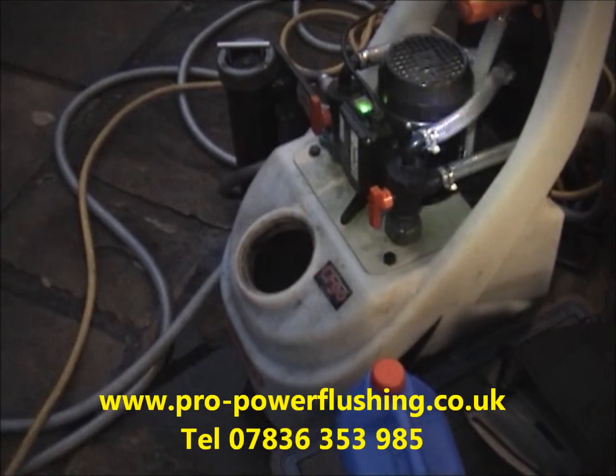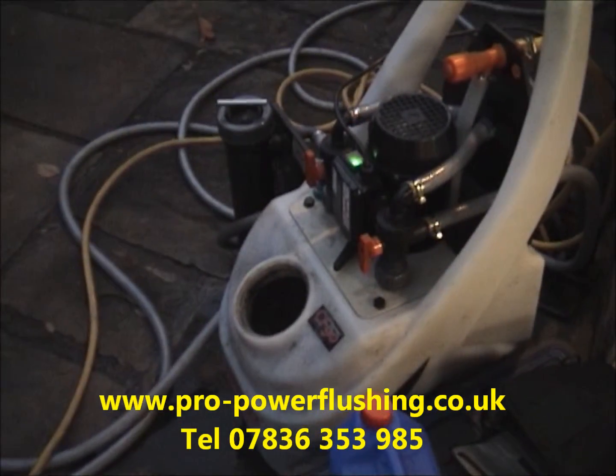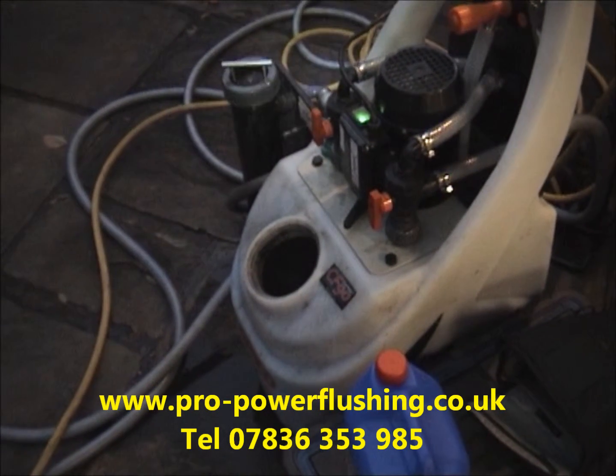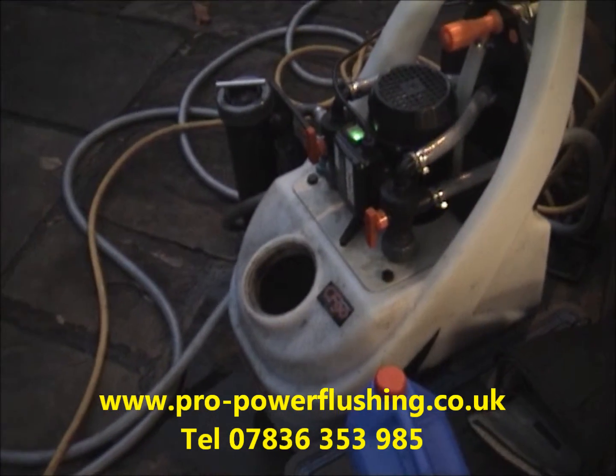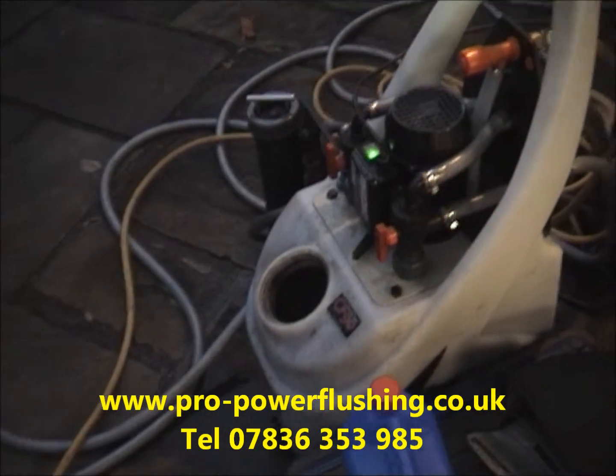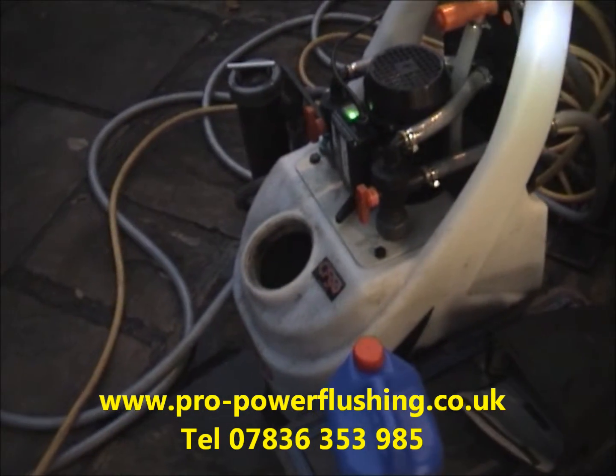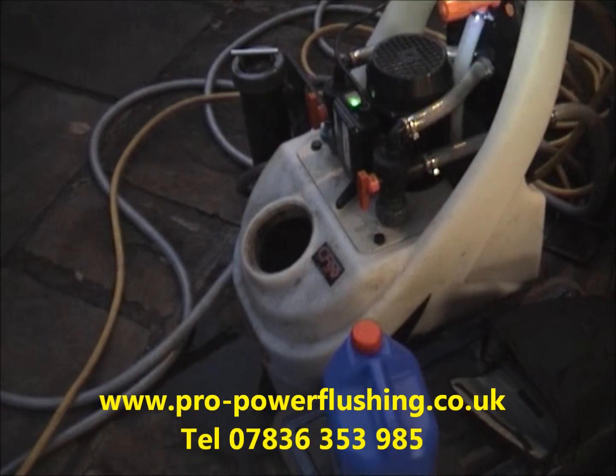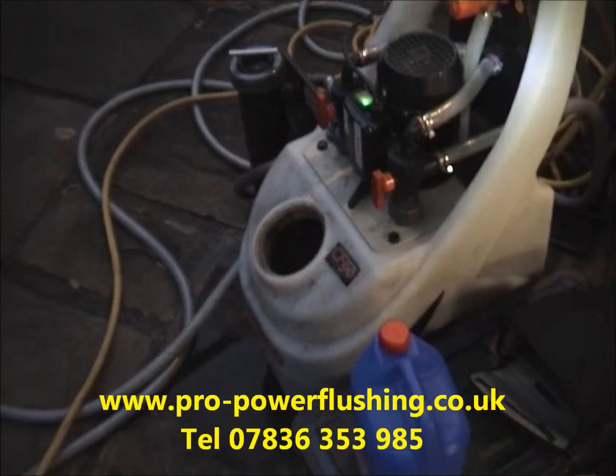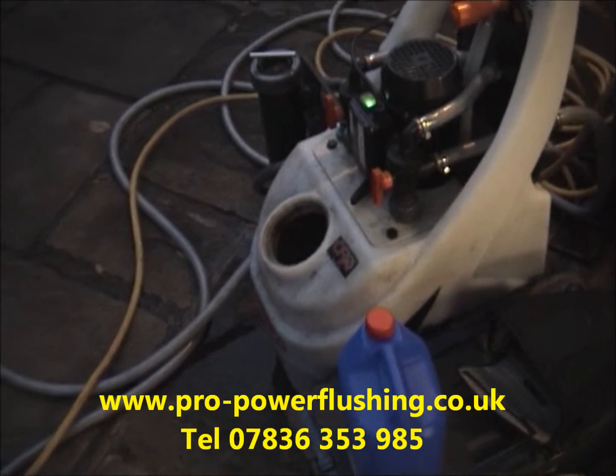We fit boilers as well. We're fitting a boiler this week for a customer in Trawden. She rang back because she had a Gledhill thermal store. To be honest with you, we can't actually power flush those systems. We turned up yesterday to flush it and couldn't do it because it's a Gledhill thermal store — they're an absolute nightmare, rust buckets, nothing but trouble. The actual unit itself can't be power flushed because it can implode. So we thought we'd mention that just in case anyone's got a thermal store. She wasn't aware that she had one — she thought she had a combination boiler, but it's not. She was a Scottish Power customer and they told her to get it power flushed, but in all honesty, you just can't power flush those systems.